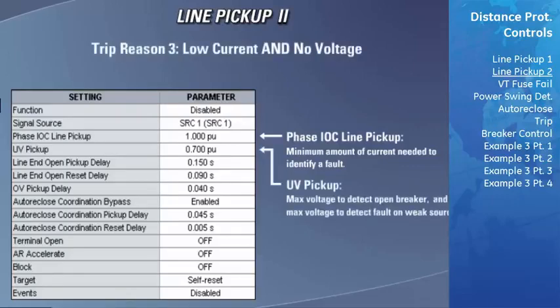The undervoltage pickup setting has two purposes. This setting defines the magnitude that the voltage must be below in order for the arming of the line pickup element to occur. This setting is also used to set the maximum amount of voltage that can be present to adhere with the third method of detecting a fault that has low current levels and no voltage on a system with a weak source. This setting should be set below the minimum voltage under normal conditions.